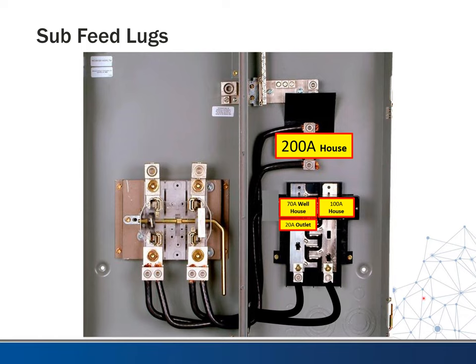So here's an example. It's not in a panel board, but it's in a disconnect. I guess this is a small panel application, like you would see, like they said here, at a well house or some exterior load. So you can see they come in here. This is where the main would connect. You come to this disconnect, which could be fed through these lugs to something else. But then you come off this double lug over to this where you could put some circuit breakers. So this is a sub-fed lug or a double lugged connection right here.